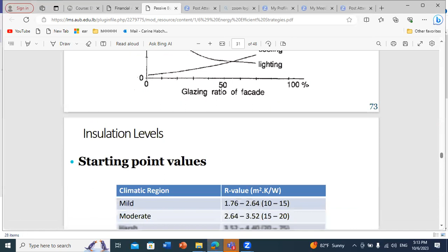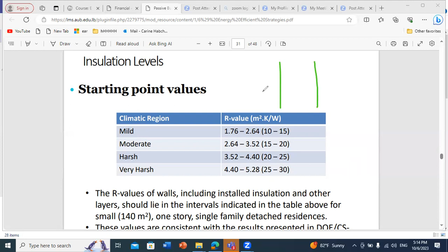For moderate climate, the resistance values will be much smaller than harsh and very harsh climate, because in extreme conditions you should insulate much more than in mild and moderate climates. Whenever you have extreme conditions, you should avoid as much as possible interaction between the inner and outer environment, because delta T is really high. In extreme cold conditions, T in is much larger than T out, and you don't want dissipation of heat from the inner space to the outer space. You should use appropriate insulation levels to avoid a drop in temperature in your inner space for extreme cold cases. For extreme warm cases, it's exactly the opposite.